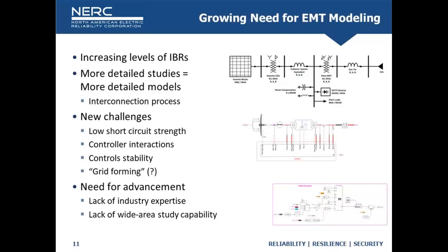We're seeing a growing need for EMT. We've had a number of grid disturbances in North America and around the world where EMT-type things have happened, in terms of low short circuit strength, controls interactions, control stability. We've continued to hear about these concepts of grid forming. What does that mean? How do we model it? But really what we're seeing is that with increasing penetrations of inverter-based resources, we need much more detailed studies, and with those detailed studies come more detailed models. We really need that during the interconnection process.